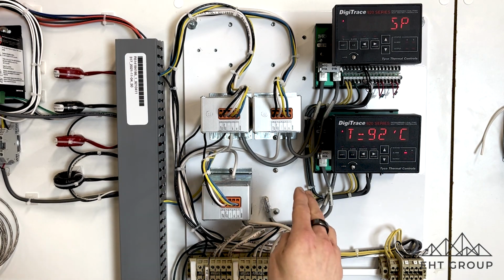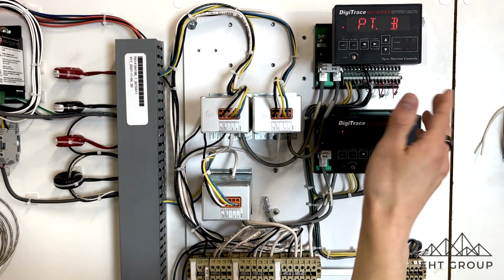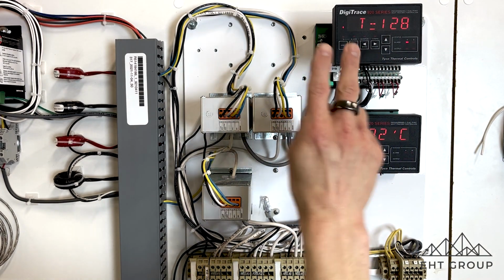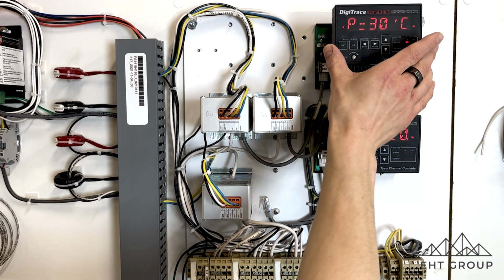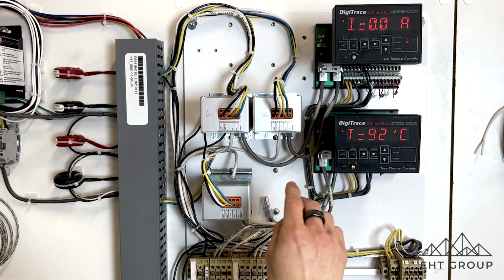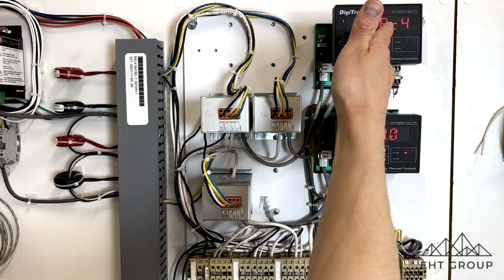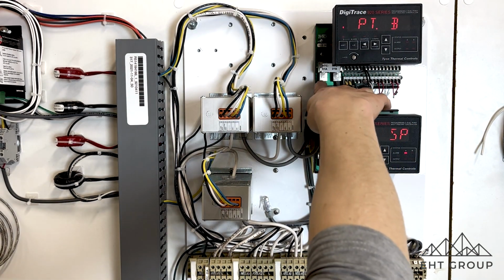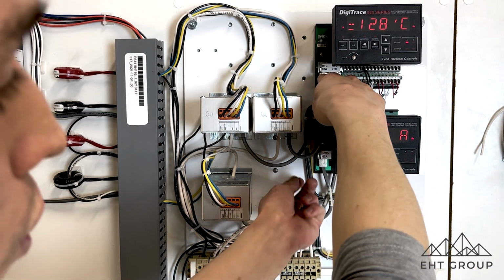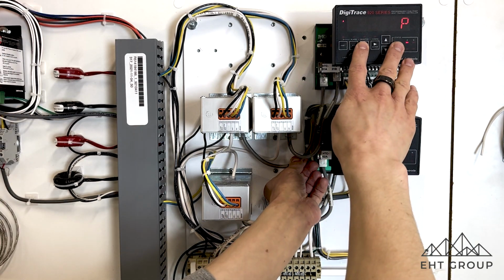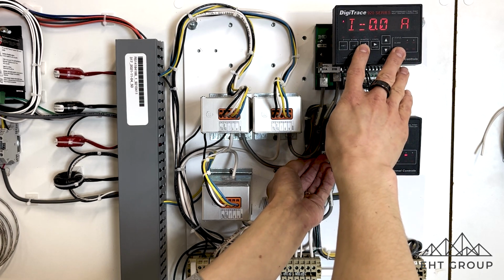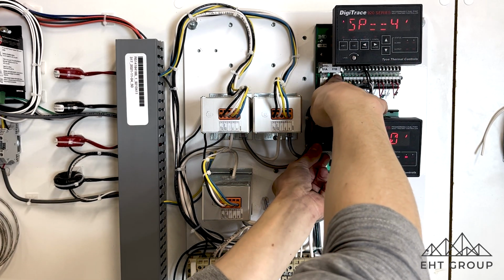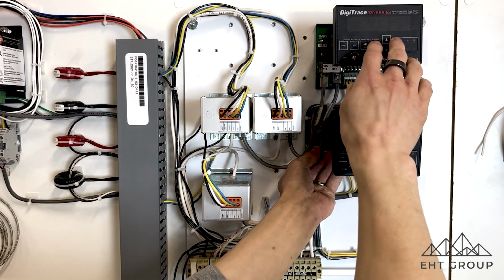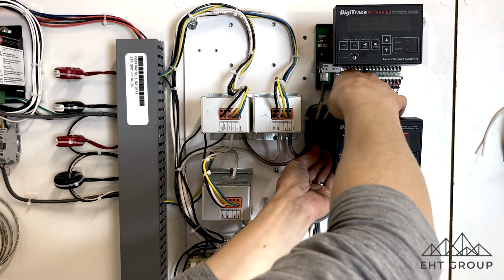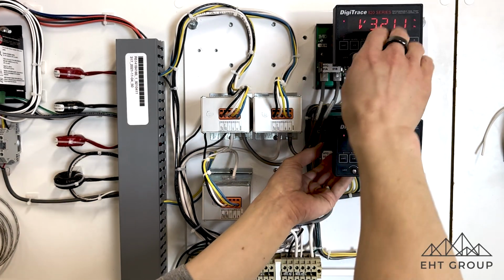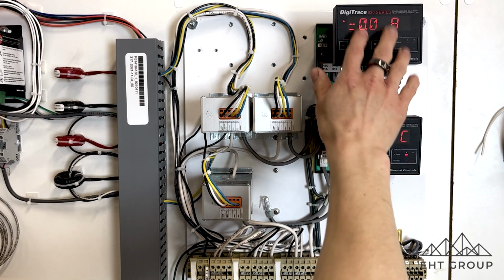So one thing to note here is that the 920 controller, you probably already know, is a 2-point heat trace controller. That means there are 2 individual heat trace circuits on the 920 module, and you get a CT module per circuit. And what you'll notice is that with these connectors on the board, if one is disconnected, we still have control voltage on the 920 module. But if both are disconnected is when we lose control power. If we have power from either one, then we get control voltage on the module.